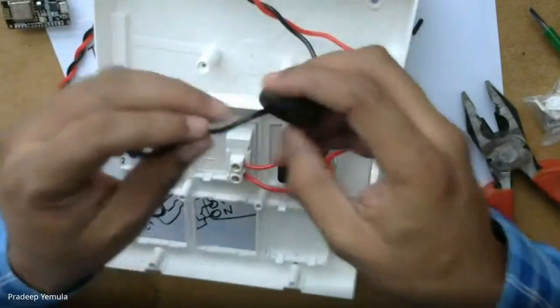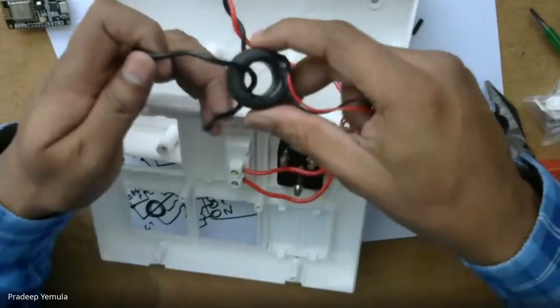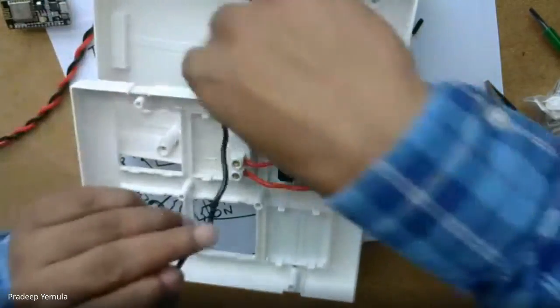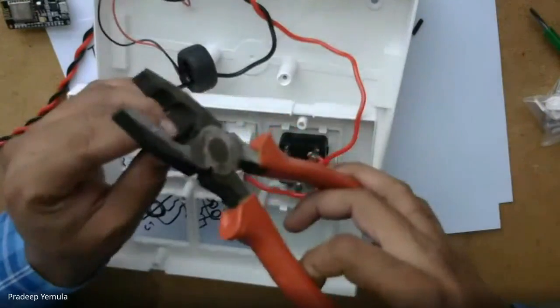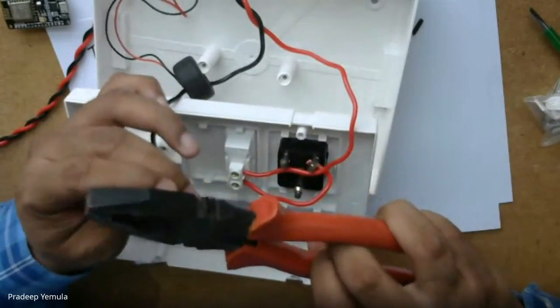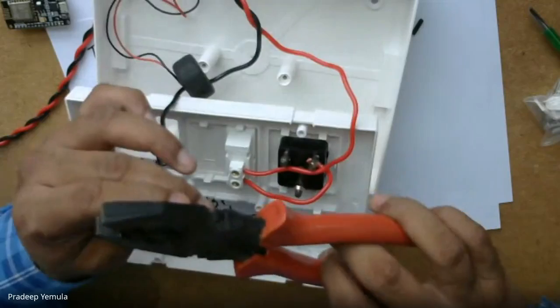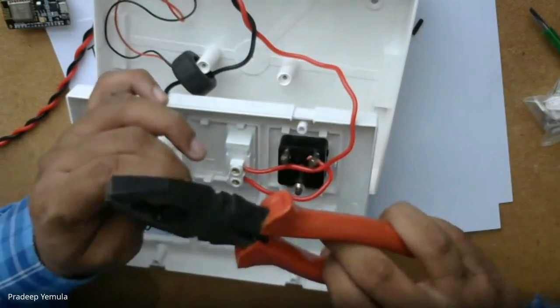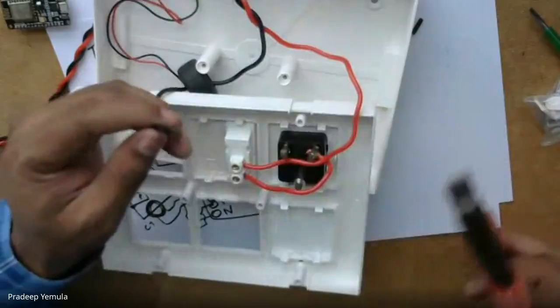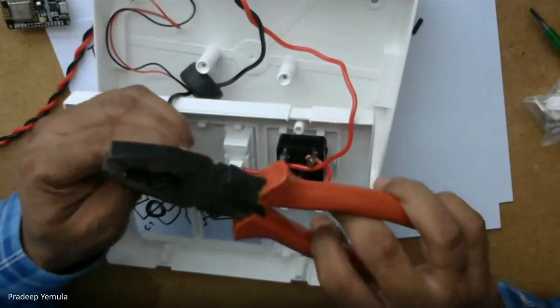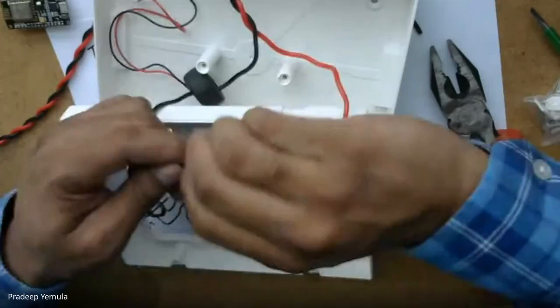But notice how I installed this current coil. It is like a current transformer. You have to keep it like this, then it will measure the current. Normally an ammeter will be connected in series, but here because it's made up of a current transformer, it is like that. Okay, I think now we are done.